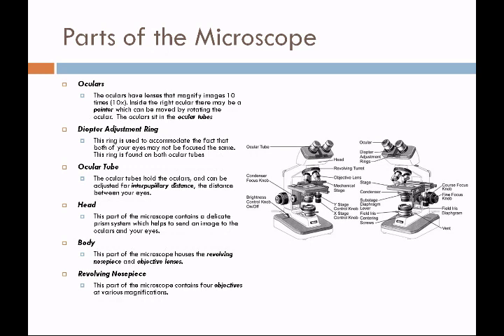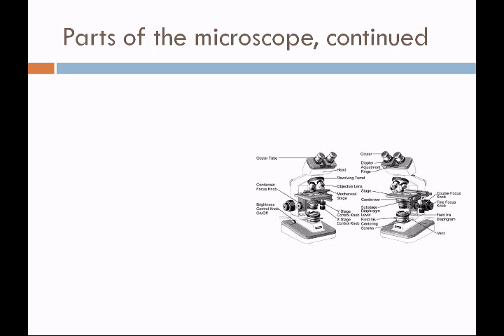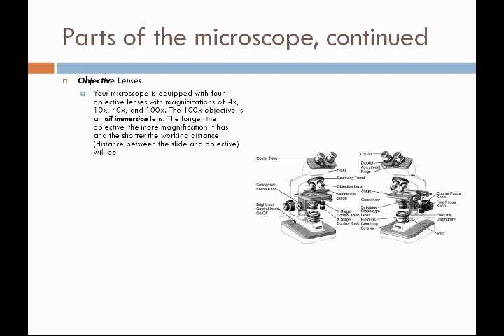The revolving nosepiece contains four objectives with various magnifications. Typically we'll find a 4x, a 10x, a 40x, and a 100x. This 100x objective is special — it's an oil immersion lens. It's a longer lens and it can only be used with oil. No other lens on the microscope is going to be used with oil. The longer the objective, the more magnification it has, and therefore it's going to be very close to the slide. The distance between the slide and the objective is called the working distance, and you always have to pay attention to it so you don't smash your slide or damage the objective lens.